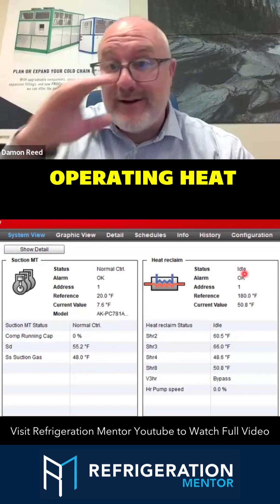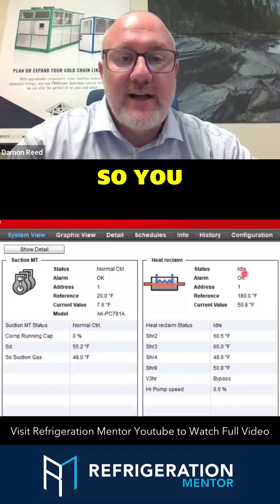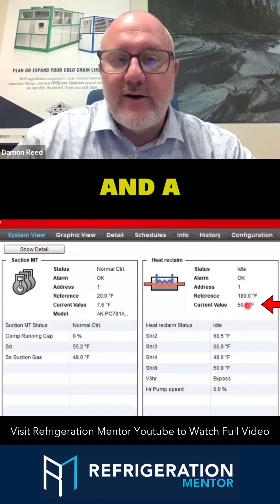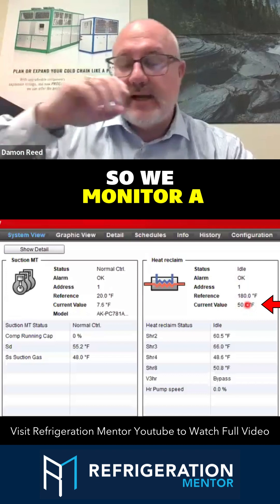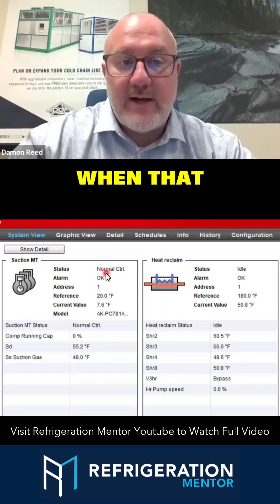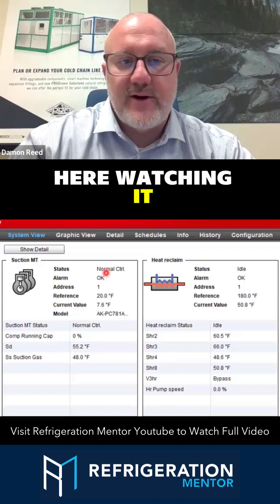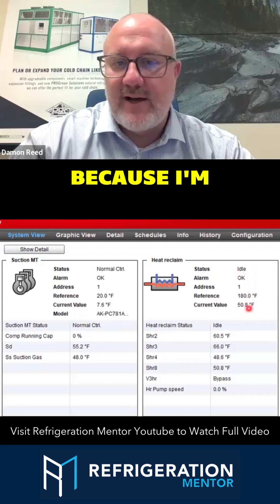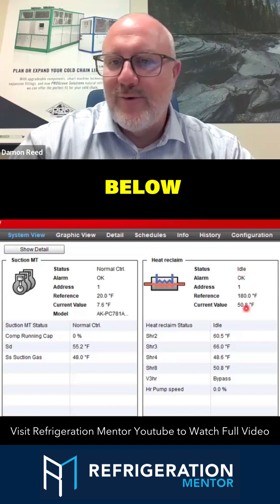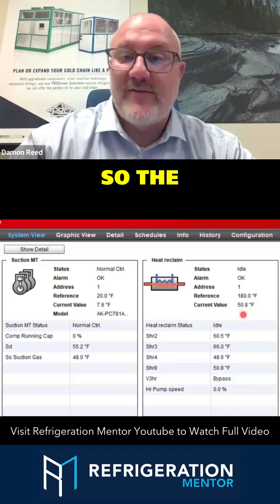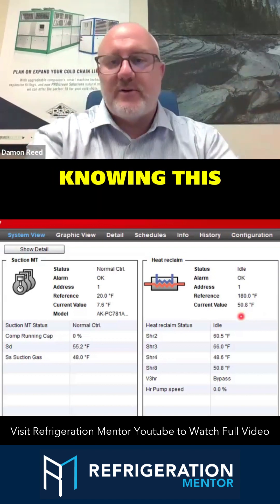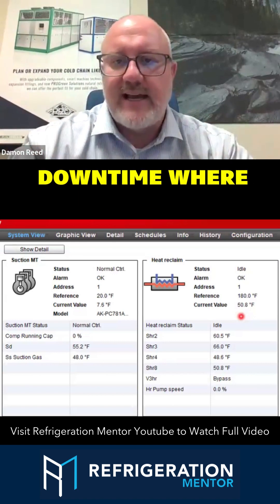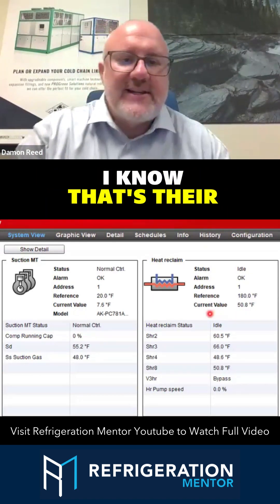Why would I be operating heat recovery if my compressors aren't doing anything? Status is okay. I've got a reference value of 180 and a current value — we monitor a remote sensor. When that compressor starts, I expect this to go into heat recovery mode because I'm 130 degrees below my reference point. Knowing this particular customer, they're just in a down period — they have hours and hours of downtime where they're not in operation.